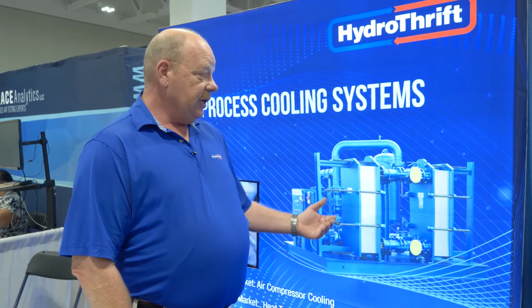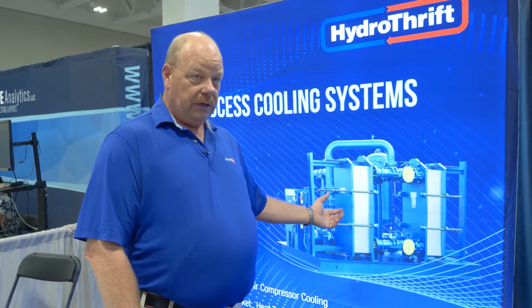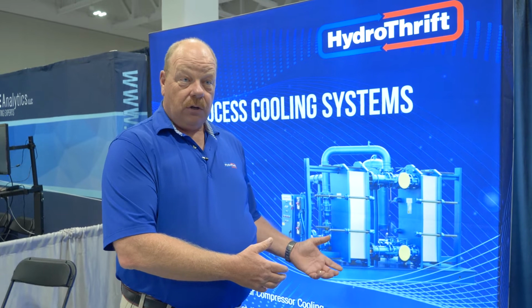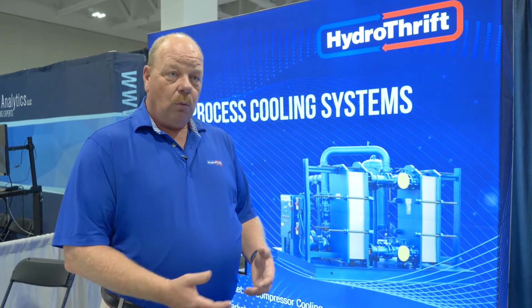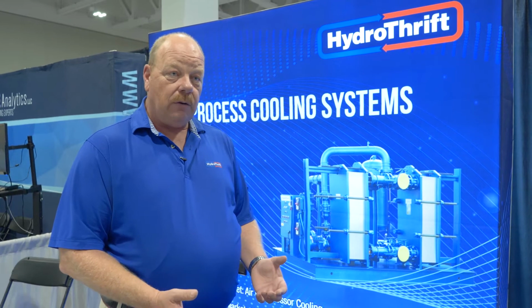The other thing that it does is it actually reduces the amount of fouling because the surface temperatures in these heat exchangers are 85 to 90 degrees Fahrenheit, whereas in a compressor it's 300 degrees Fahrenheit. At 85 or 90 degrees, the mineral content in the water doesn't have a chance to plate out and foul the heat exchanger. So actually your air compressor will run much longer without fouling or scaling.